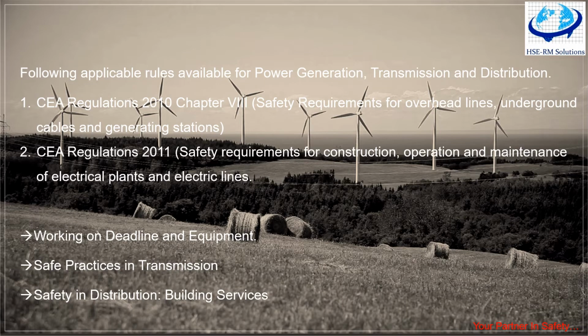Now, minimum vertical clearance between any conductor and guard wire should be 300 mm for low and medium voltage, and 600 mm for 11 kV, 900 mm for 33 kV, 1.2 meters for 66 kV and 1.8 meters for 110 kV lines. Now choke coils are also sometimes used.